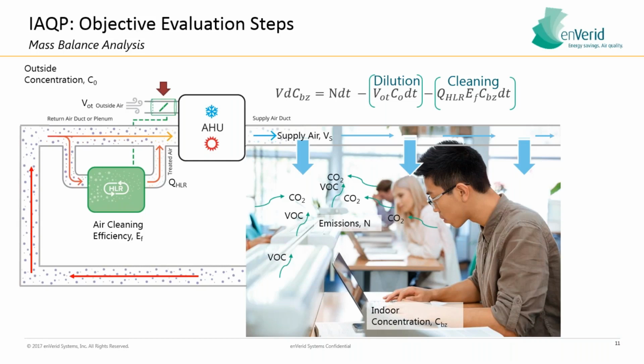So one enVerid HLR is good for about 150 design occupants. And you can apply one HLR for those 150 occupants, and you're going to end up being able to drive outside air requirements down to essentially just building pressurization. So essentially the mass balance equation is up here. We know the emission rate of these contaminants according to square footage, space type, occupancy, and decades of ASHRAE research. So these emission rates are published by ASHRAE.